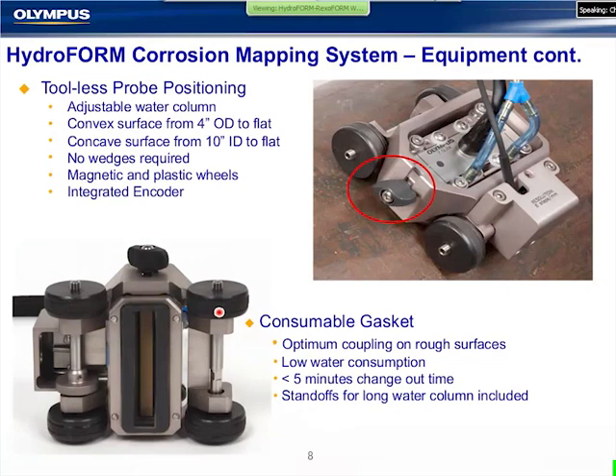In the mapper that you see here, there's a small consumable foam seal with a Teflon coating that allows the water to be contained within the column. It allows this mapper to slide over rough surfaces and some minor external corrosion to contain the water column. It needs to be free of bubbles. It takes less than 5 minutes to change out the seal. Depending on the surface condition, the production rate, and how much tension you have to put on the gasket, these seals can last a month or less than a shift and require changing. And again, it's a very short, quick change-out time for the seal.